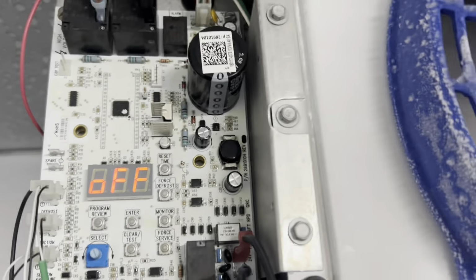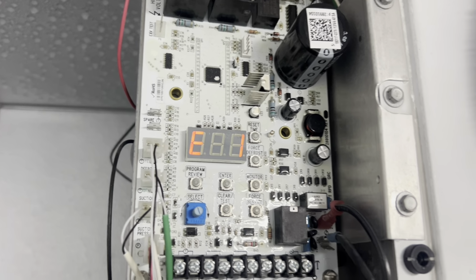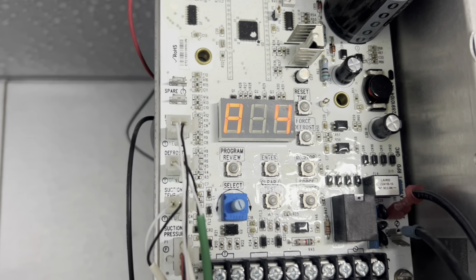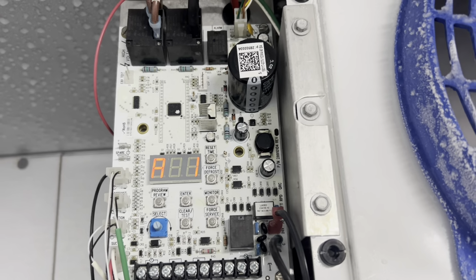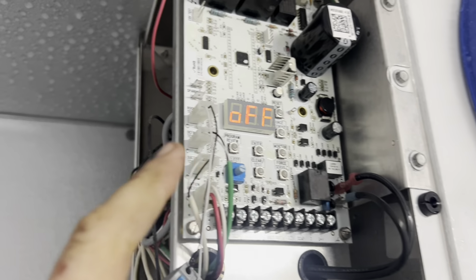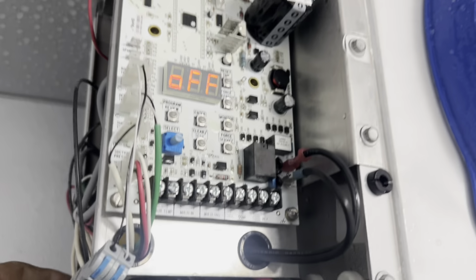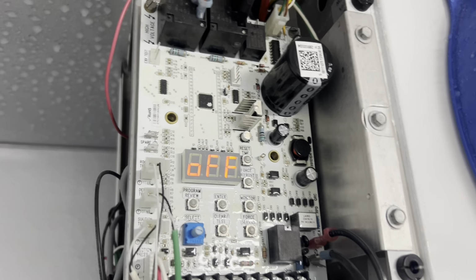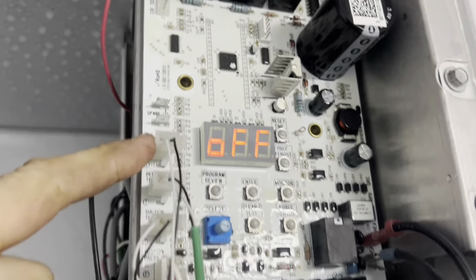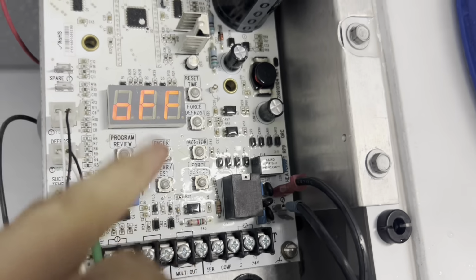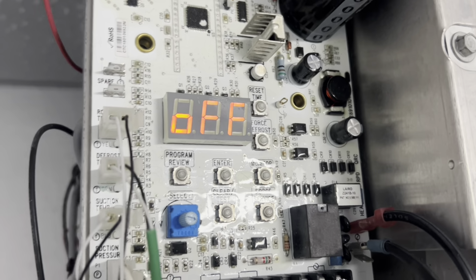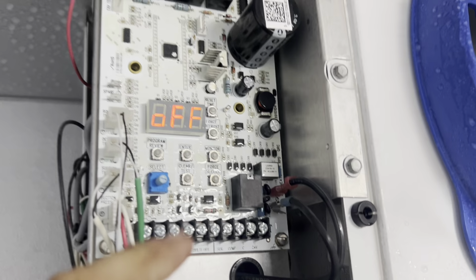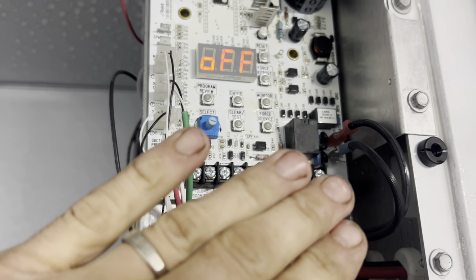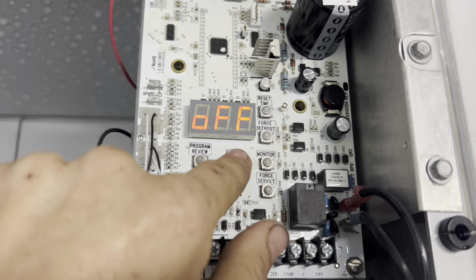All right, our favorite controller. So it's off currently, which is funny because it's freezing in here. It says it's 125 degrees. We've got E1, A1, A4. A1 is high temperature. A4 or A5, whatever it was, I don't even remember now, was probe fault, and E4 is room temperature probe fault. So I put in a new temperature probe. We're going to be on a couple minute delay. This unit has, I think it said a 4-minute delay in the book. I was just looking at it online. So she's going to sit in the off position for a little bit, and then she's going to kick in to cooling mode. Hold the door open to raise the box temp.